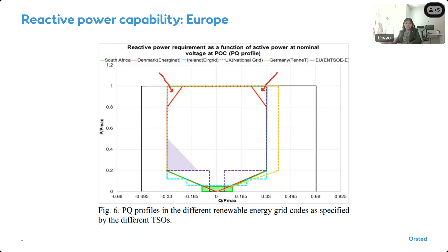I want to touch upon cost a little bit. The example I'm taking is an offshore plant of one gigawatt. For offshore wind plants, we don't expect reactive power to be exported or imported from the offshore turbines, just because of the cable capacitance and distance. It doesn't make it cost effective, and it doesn't utilize the cable ampacity very well.